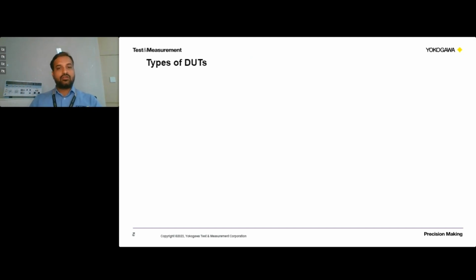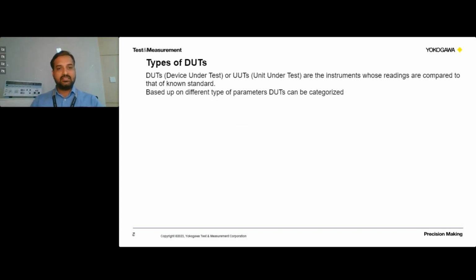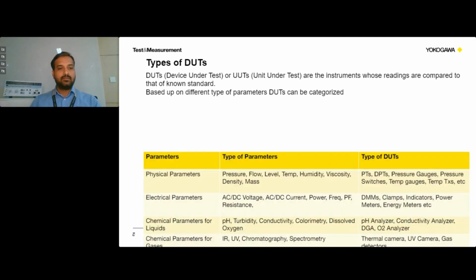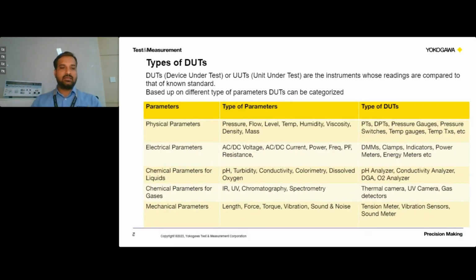Then we'll move into what are the types of DUTs we come across. DUTs are basically the instruments which are compared to the known standard or the master standards in the lab or in the field. Based upon different types of parameters, there are different types of DUTs which can be categorized. For example, for physical parameters such as pressure, flow, level and temperature, we come across DUTs such as pressure transmitters, differential pressure transmitters, pressure switches, temperature gauges and temperature indicators.